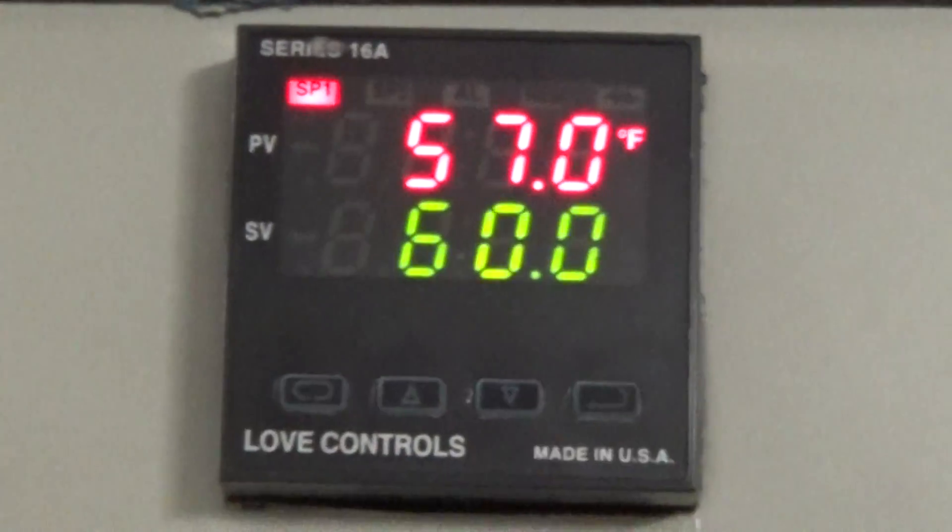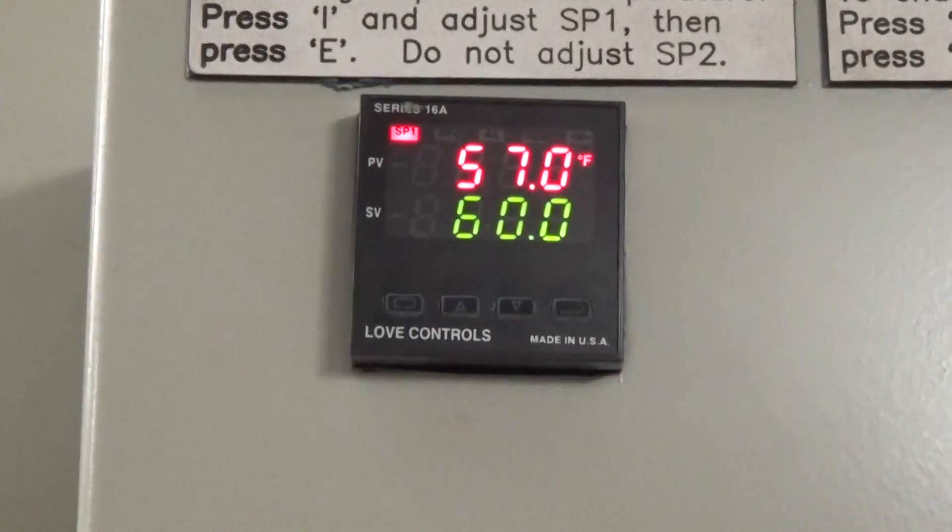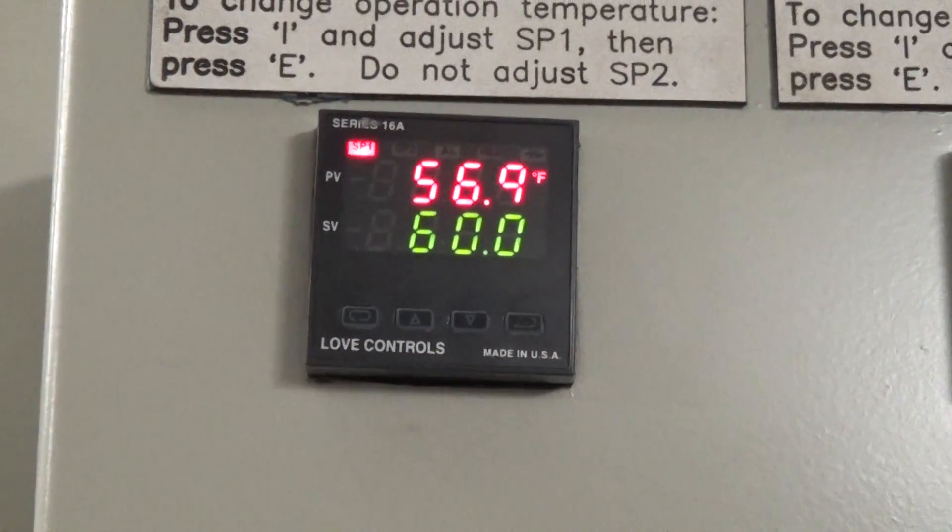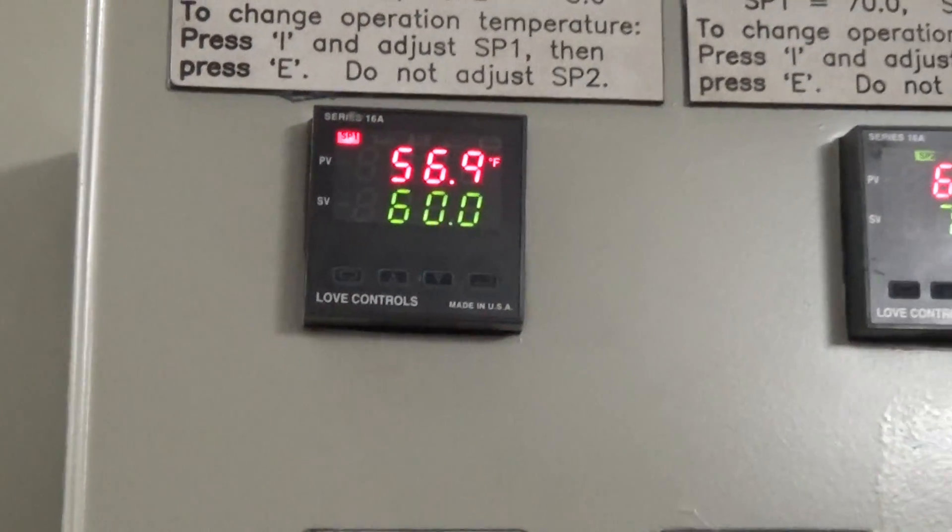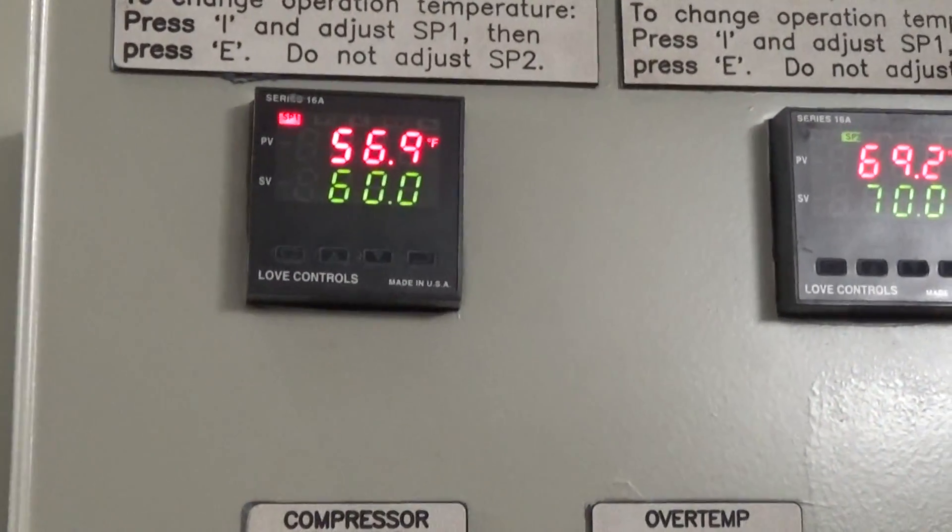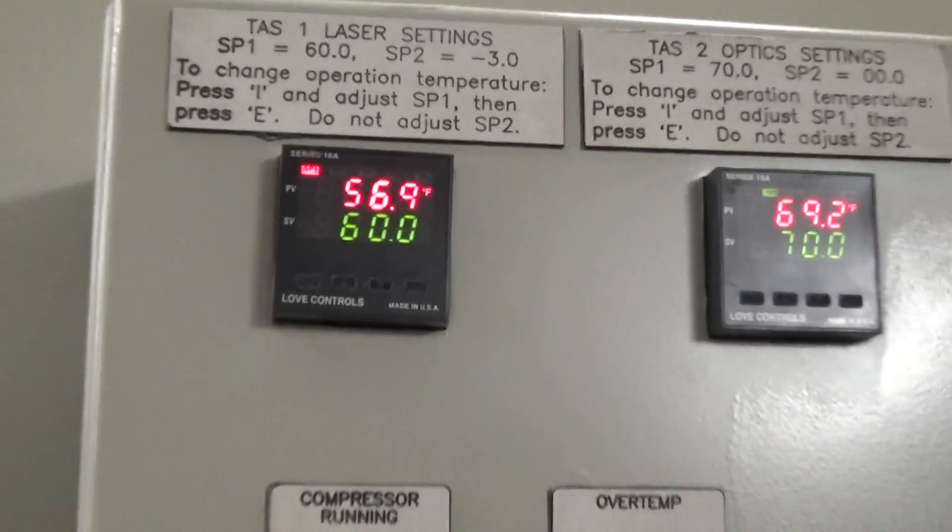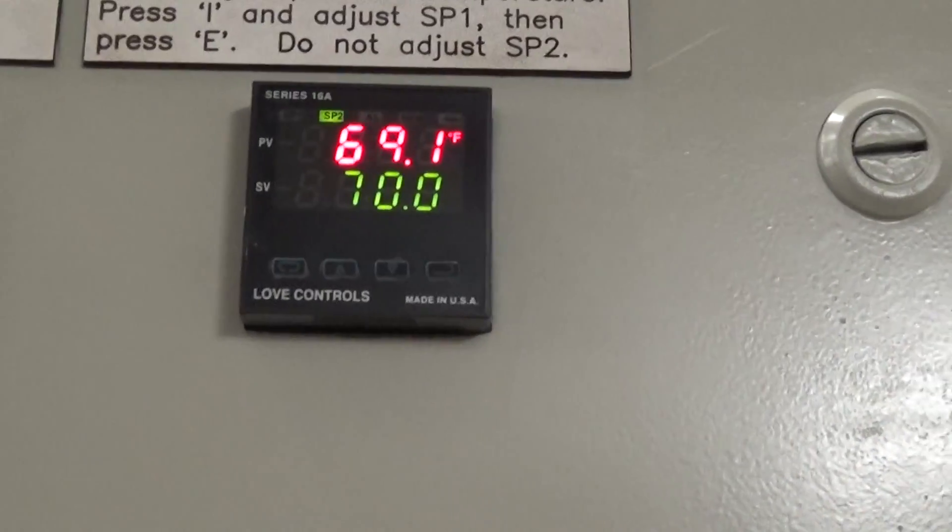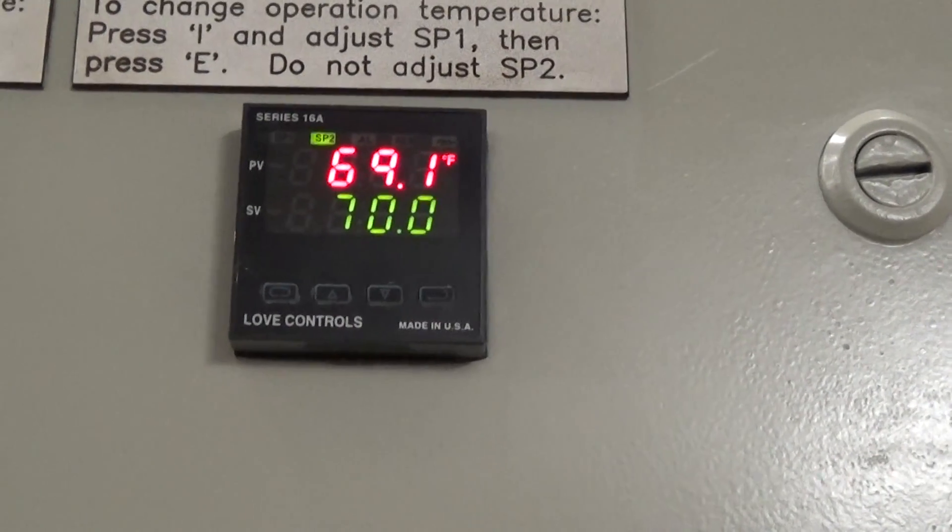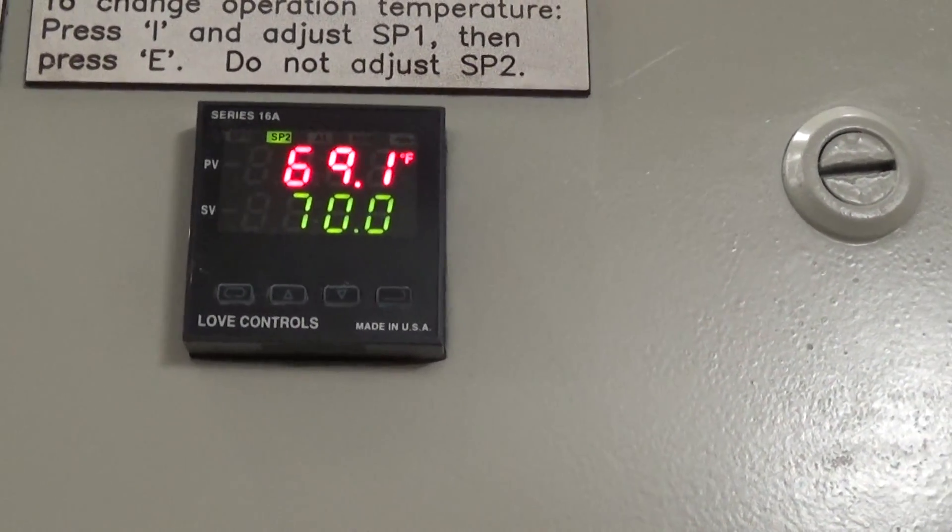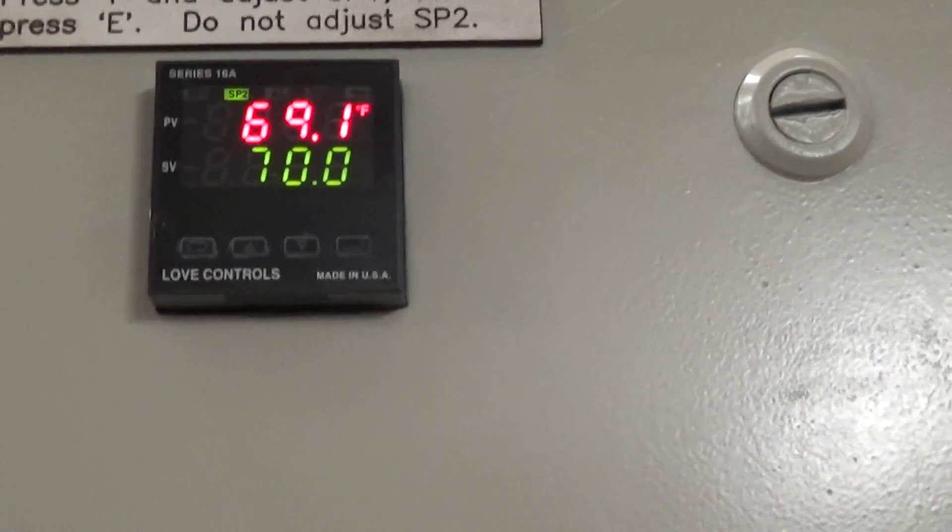So we got to our 57 degrees Fahrenheit. It will be a little bit of an overshoot. We will get up to a little bit over that 60 before the compressor turns on and it calls for cooling. And that whole time the optics will all stay within that one degree of that 70 degree Fahrenheit set point.